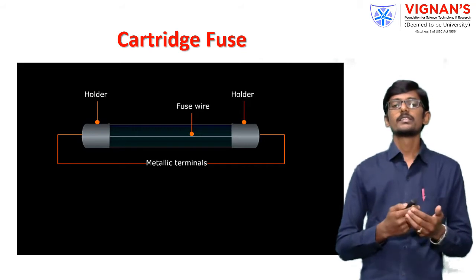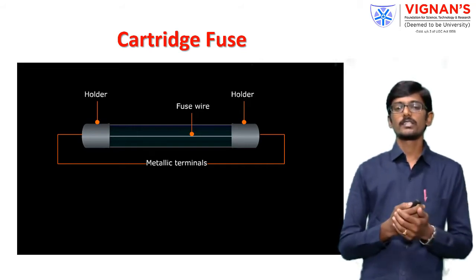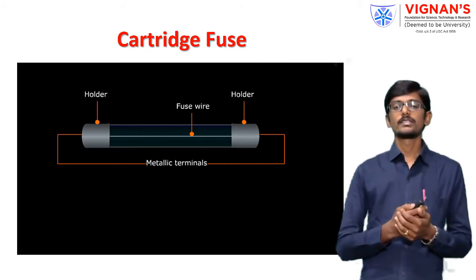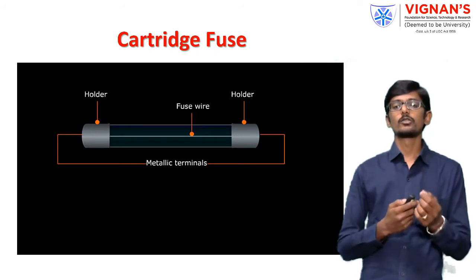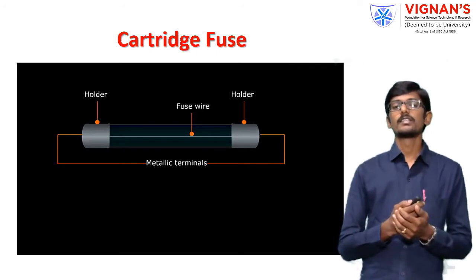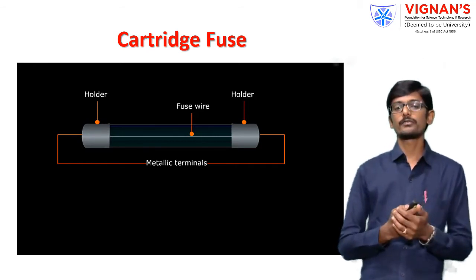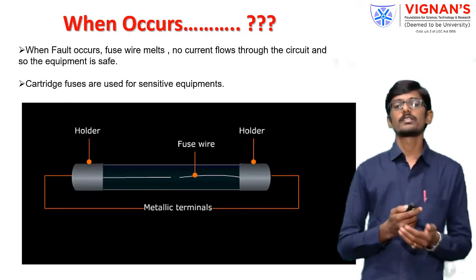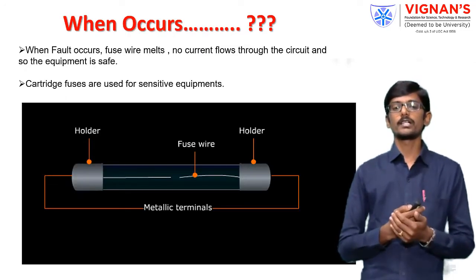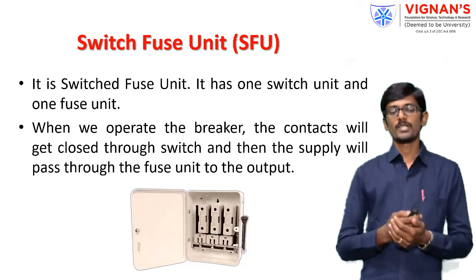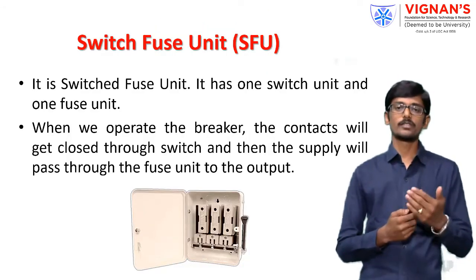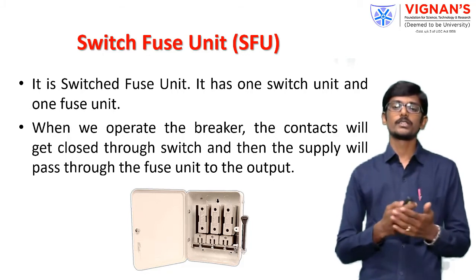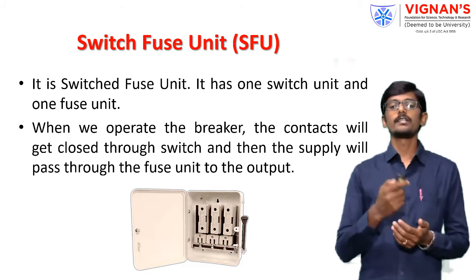It is commonly seen in stabilizers and small electrical operators, where it requires a low amount of space. It is not used for high ratings, only for small ratings. This also consists of a fuse wire which melts whenever a fault occurs on the device or from the input end. The third one is the switch fuse unit, where you can see a handle.